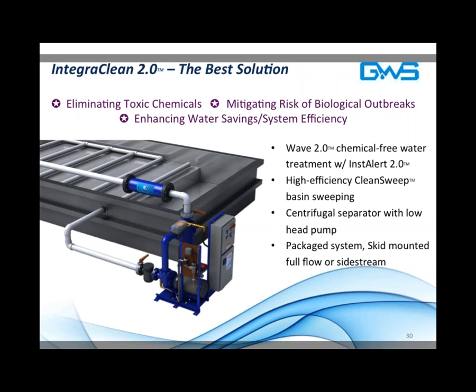What it will not do is treat the solids that have been settled in low flow areas of a system without recirculation. So those solids that have settled out and not been resuspended, for example, can serve as breeding grounds for bacteria. So the short answer is that both of these systems, when combined together, provide the ultimate in terms of water savings, which is why when we sell IntegraClean 2.0, which is the whole package you see here, we will guarantee water savings.